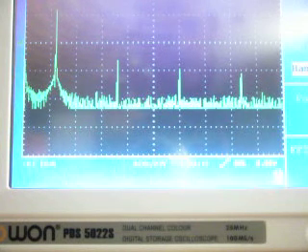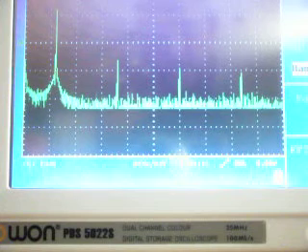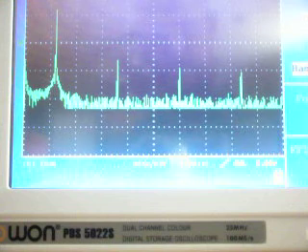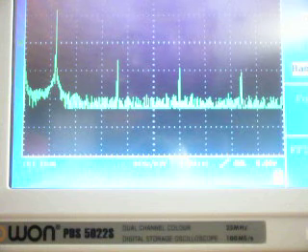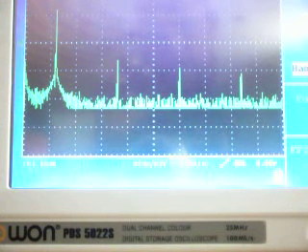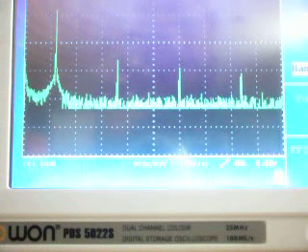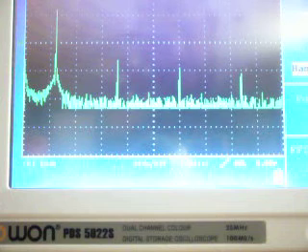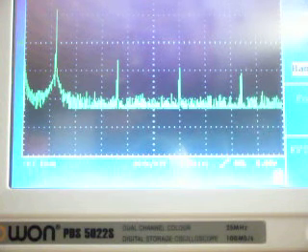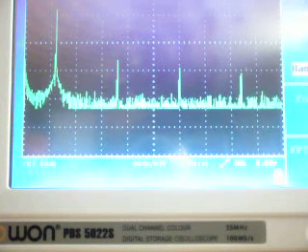As you can see, we've got a number of spikes there. The first one on the left-hand side is what you would expect—that's a 60 Hz frequency spike, the frequency of the mains system. But the others are actually not supposed to be there. They're called harmonics.